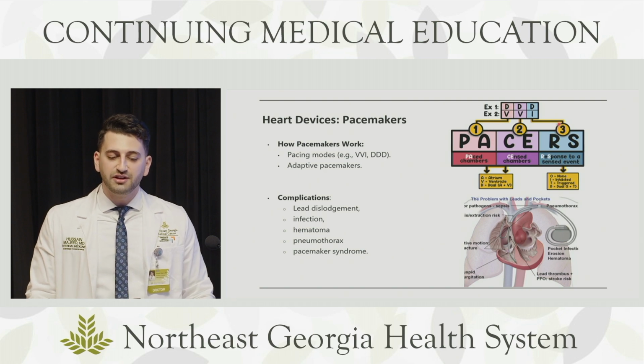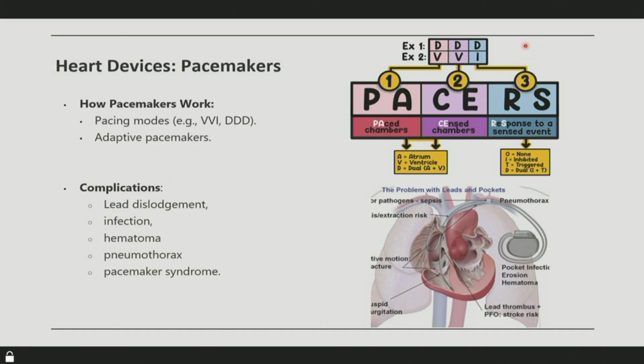The first letter, you can think about it as the chamber that is paced. So what is receiving the paced electrical shock at that point? The second letter is what chamber is sensed as a response or prior to the pacing. And the third letter is the action, what is the response to that sensed rhythm for the second letter. And we'll go over a whole table about the most common pacing methods that we can see.